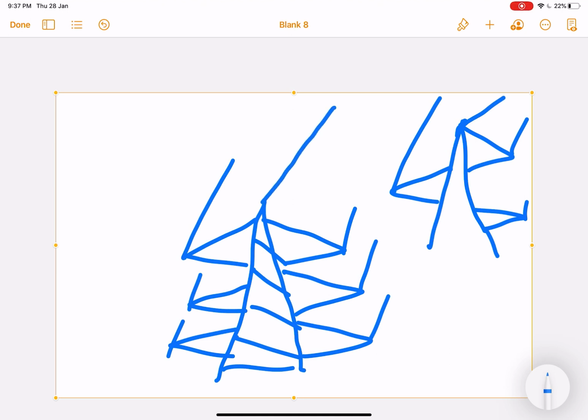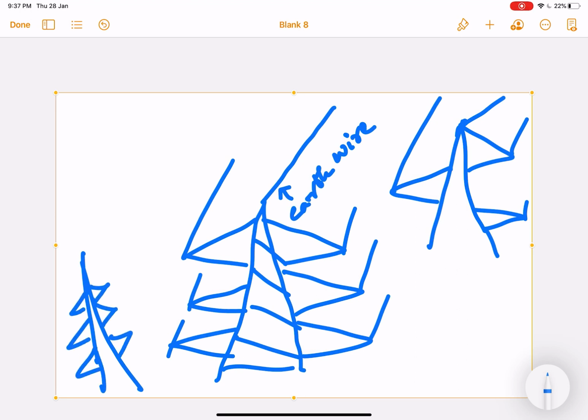This is the earth wire. It is also called a shield wire or earth wire. But what is the main criterion for calling an earth wire an earth wire? An earth wire is generally connected from the peak of one transmission tower to the peak of another. It is very thin, and it is connected to the tower body through a small copper bond.